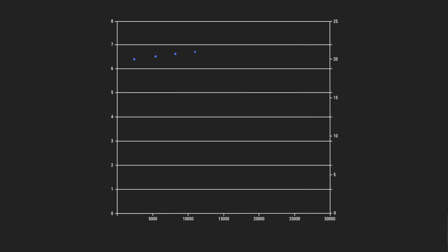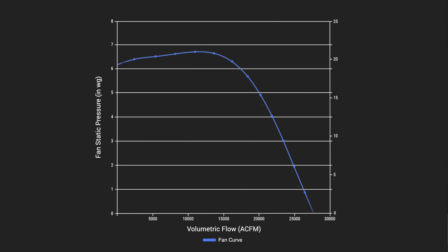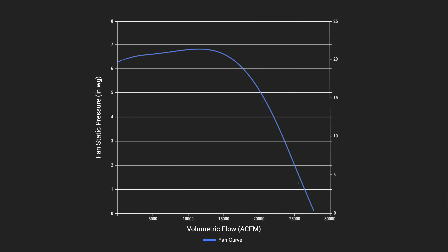Each fan has a unique curve showing a spectrum of potential operating points called a fan curve. Each potential operating point shows the amount of airflow and pressure a fan generates at that point. Changing the fan speed shifts the fan curve either up with a speed increase or down with a speed decrease.